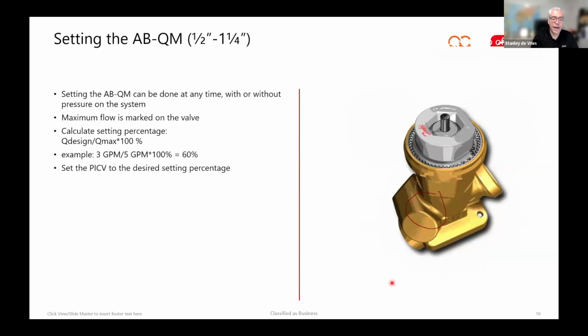Also, usually when we have a number of different valves, I will show you the full lineup later. Let's say there is a 1/2 inch valve that we have, or actually there are two, and they have a maximum flow, I don't know, could be 4 or 5 gallons per minute. But you don't always need 5 gallons per minute. Maybe you need 3. So then it becomes quite a simple calculation. You calculate what percentage 3 gallons per minute gives you from 5, which is 60%. And then you just lift the top and set the flow to the right value.